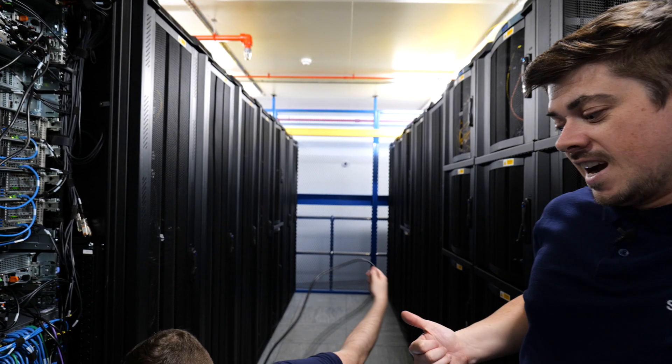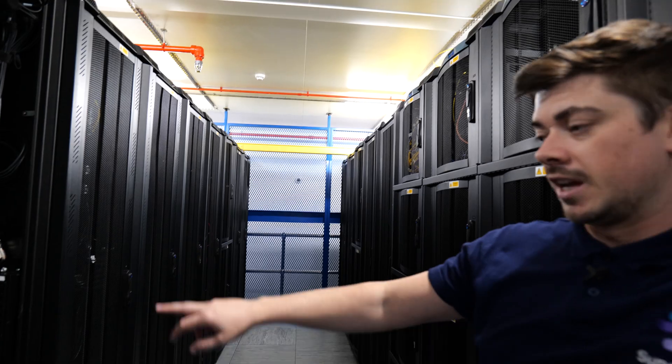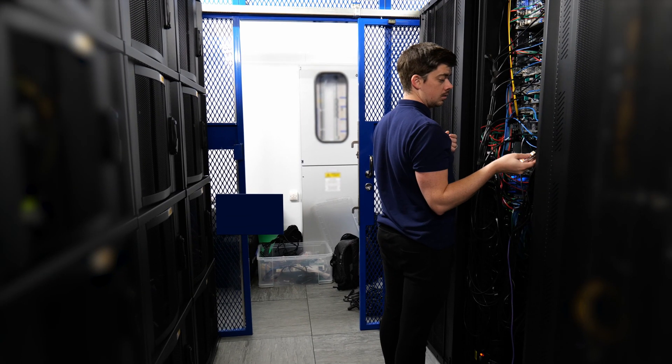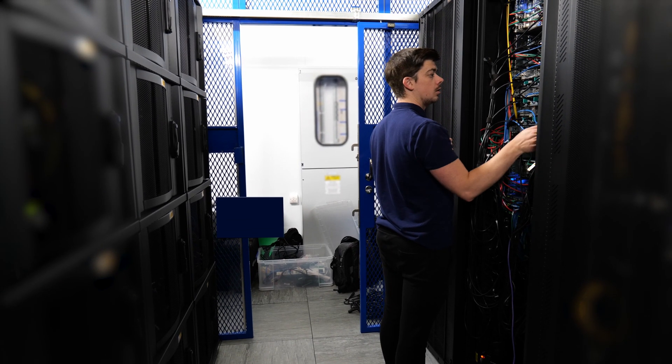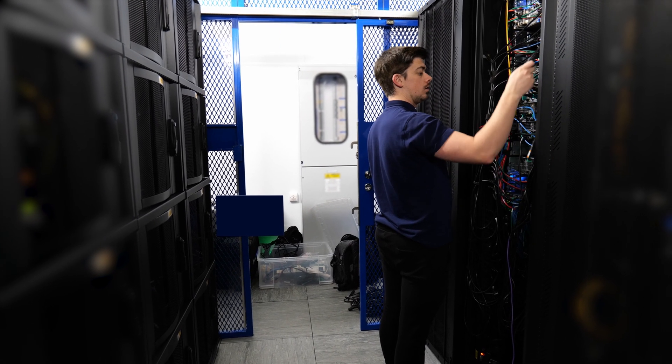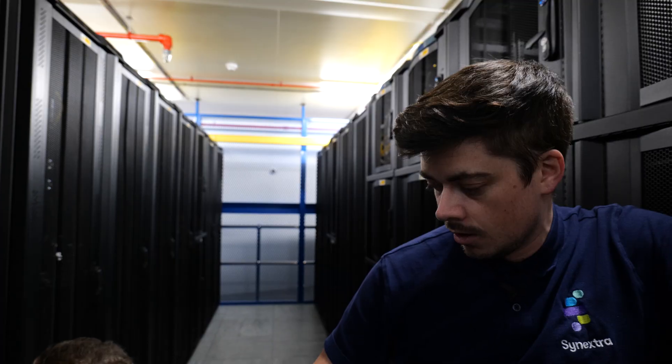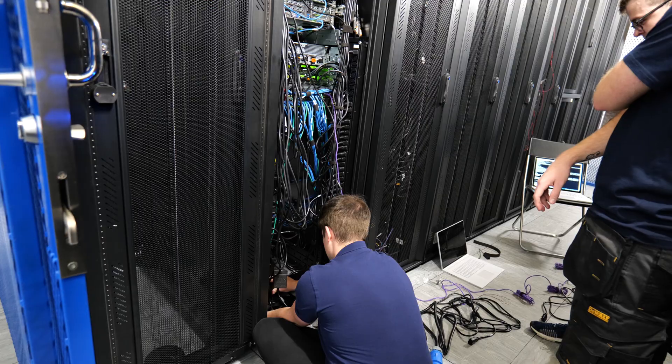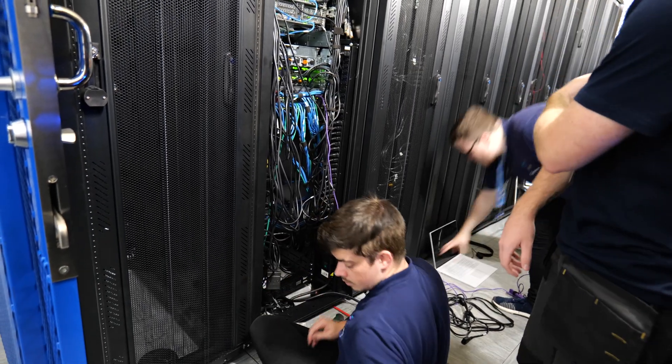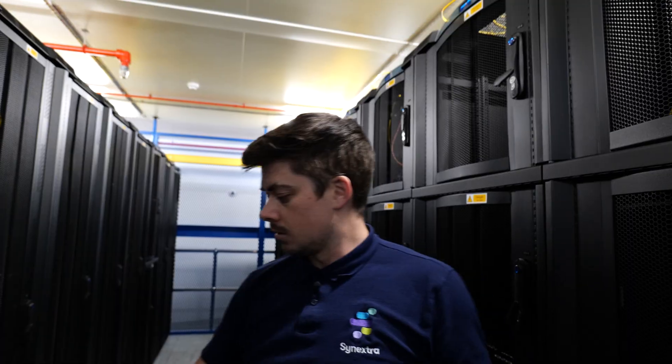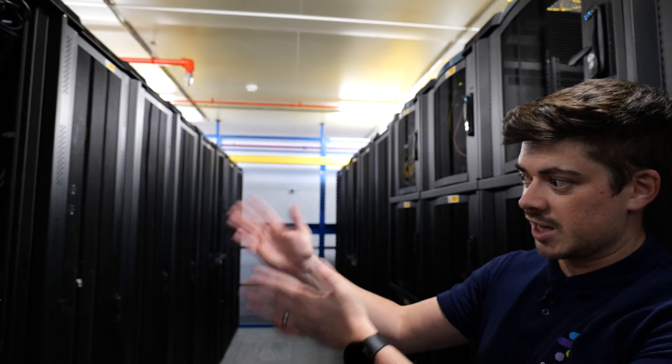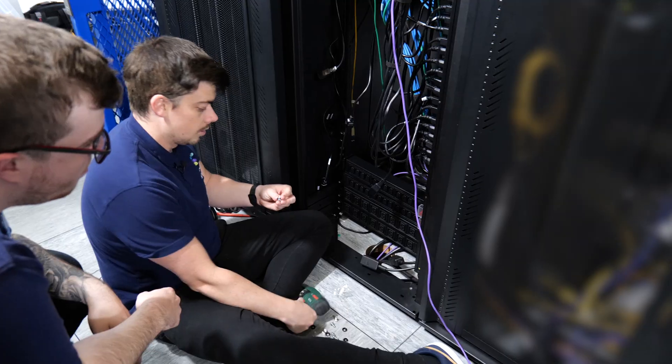Bit of a tidy up for one, to make sure everything is plugged in properly and redundant in the A and B. There was a couple of things that were not correctly wired, and then the two PDUs that we put into the bottom there were metered, so they actually show the power draw. The cabs being so narrow, having everything down there as opposed to blocking your servers just makes the management of everything a little bit easier as well.